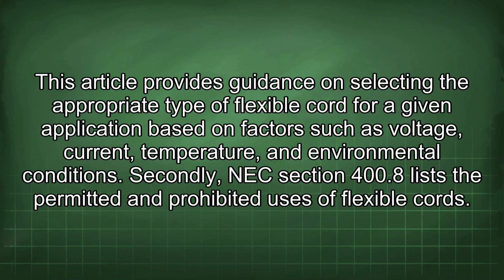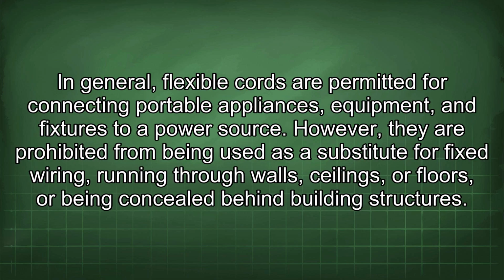Secondly, NEC Section 400.8 lists the permitted and prohibited uses of flexible cords. In general, flexible cords are permitted for connecting portable appliances, equipment, and fixtures to a power source. However, they are prohibited from being used as a substitute for fixed wiring, running through walls, ceilings, or floors, or being concealed behind building structures.